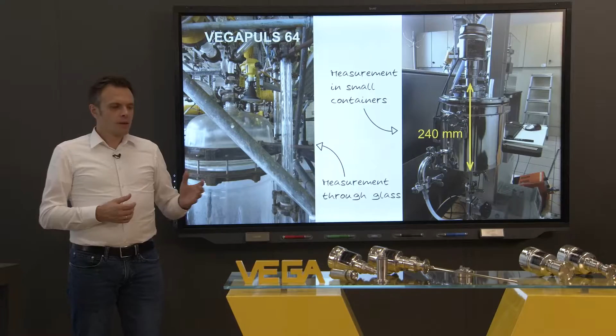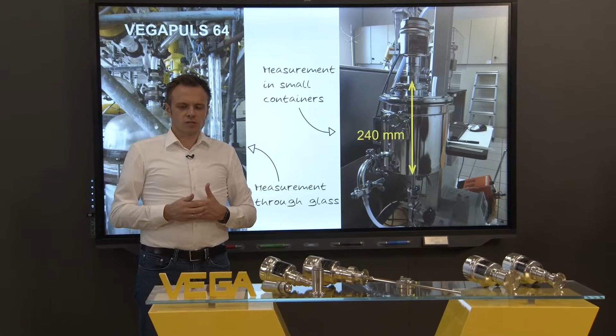The second application I want to show to you, it's in a laboratory. We have a very small vessel, only 24 centimeter measuring range. Because there's no blocking distance with the 80 gigahertz antenna, we can measure the full measuring range. This example shows you that you can use the VEGAPULS 64 in the laboratory with the very beginning of your development of a pharmaceutical device, pharmaceutical ingredient, and when you scale it up in your process, you can use still the same sensor. You have still the same evaluation for the sensor from the laboratory up to your upscaled production.